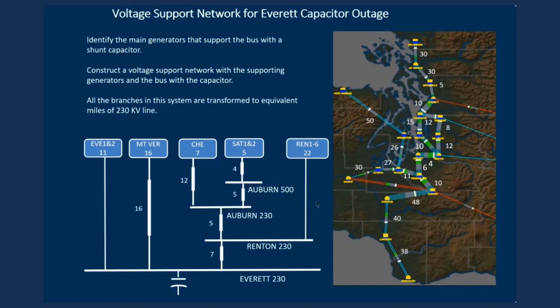So we'll be building an electrical distance diagram that really takes everything in the Cascadia system. It takes lines that are parallel and combines them into a shorter line. It takes 500 kV lines and makes those into shorter 230 kV lines. And it takes the transformer and moves those to an equivalent line length. And so that's what you're seeing here.